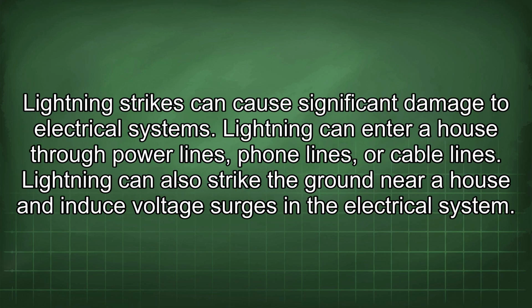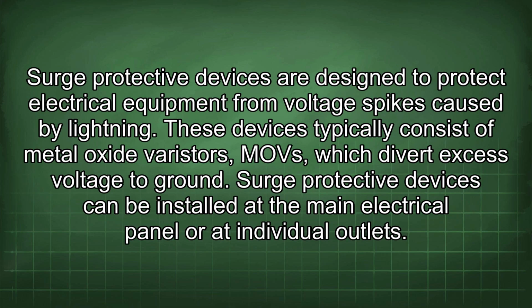Lightning strikes can cause significant damage to electrical systems. Lightning can enter a house through power lines, phone lines, or cable lines. Lightning can also strike the ground near a house and induce voltage surges in the electrical system. Surge protective devices are designed to protect electrical equipment from voltage spikes caused by lightning. These devices typically consist of metal oxide varistors, MOVs, which divert excess voltage to ground.